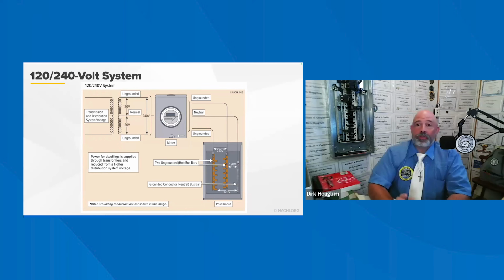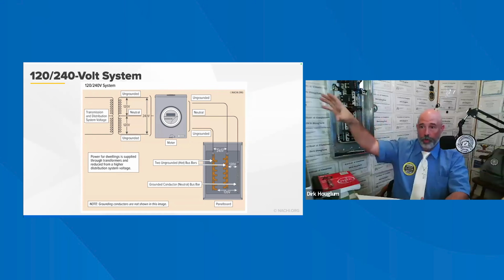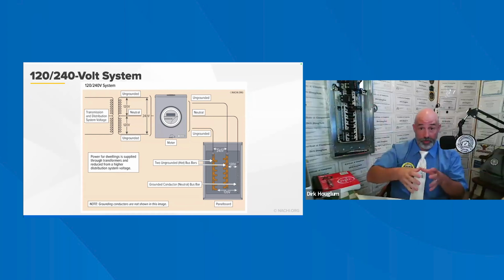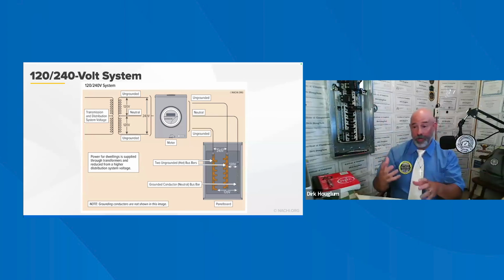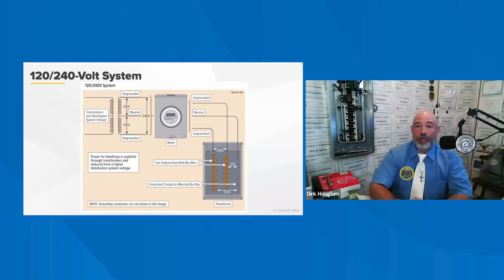Most homes in North America use a 120 to 240 volt split phase system. Power comes from the transformer on the utility pole and runs down to the house through a service drop. That is a bundle of wires you see overhead. It includes 120 volt hot wires and neutral wires. Sometimes there's also a messenger wire that helps support the line. The neutral wire from the pole is grounded at your home, usually by a metal rod driven into the earth near the service panel. This setup allows you both 120 volts and 240 volts in your home. When you connect something between the hot wire and the neutral, you get 120 volts per side.